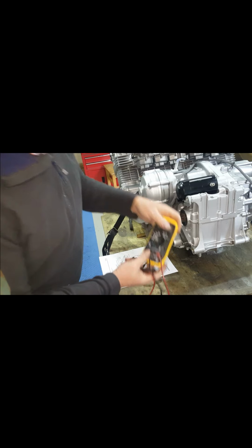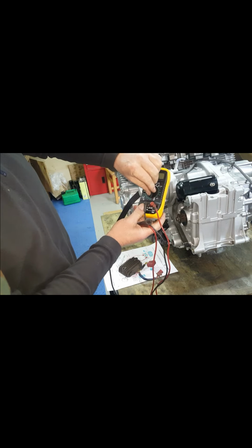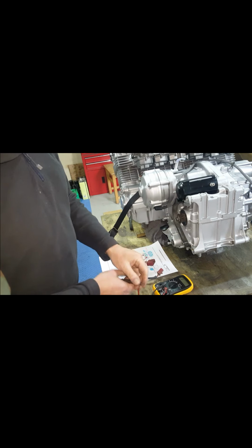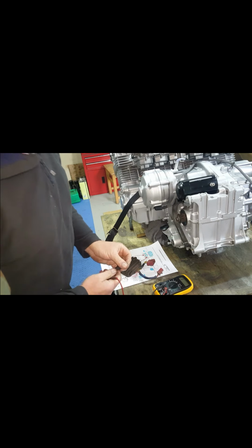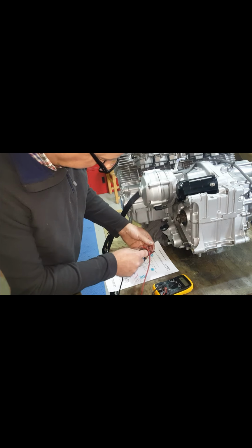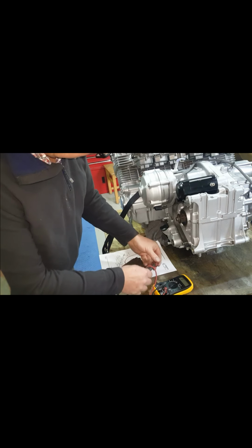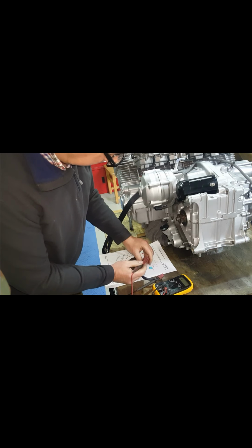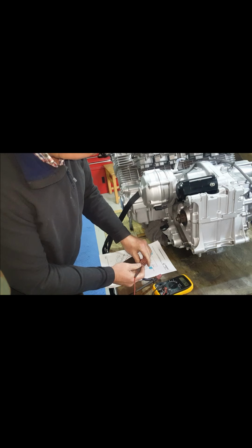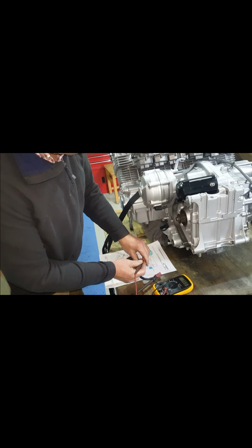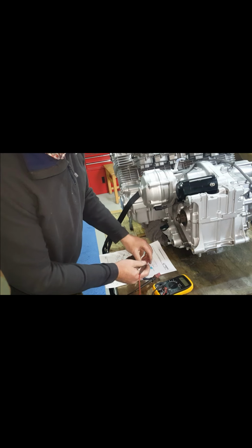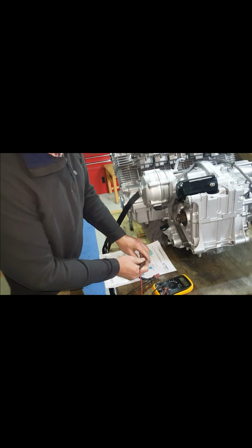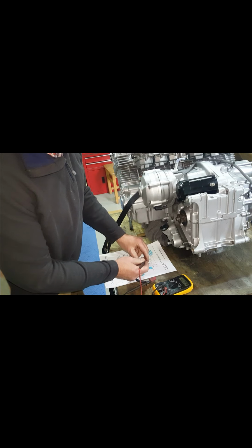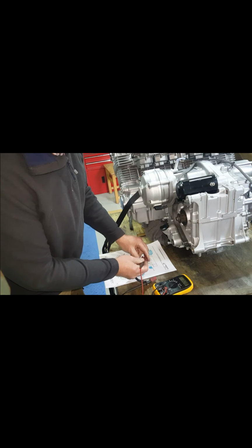So now we're going to take our probe. First and foremost, we're going to put our meter onto this setting here, which is test diodes, and that's also continuity test. When you put that on, you hear the buzzer go. Now we're going to put the black lead into the red wire. What we're looking for is a reading of about 360 across these diodes. So we're seeing 366 there. Sometimes this might be up to 500, but really what you're looking for is consistency across all the 6 diodes, because you can see there are 6 diodes here. So we're getting 360 across all of those diodes that way.